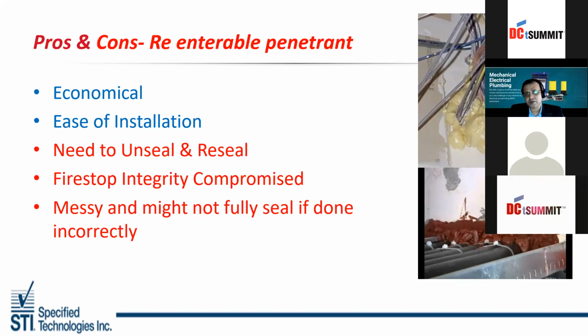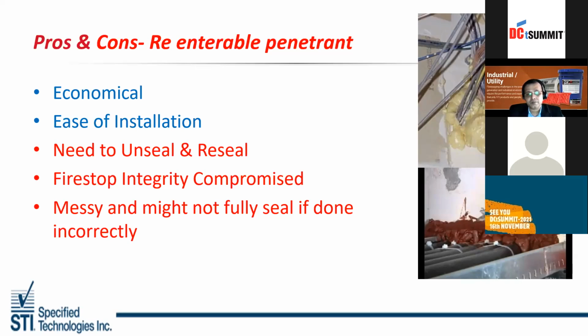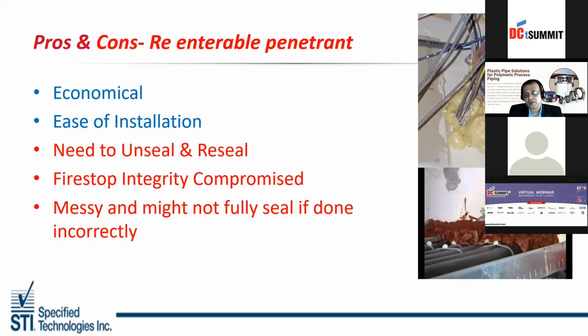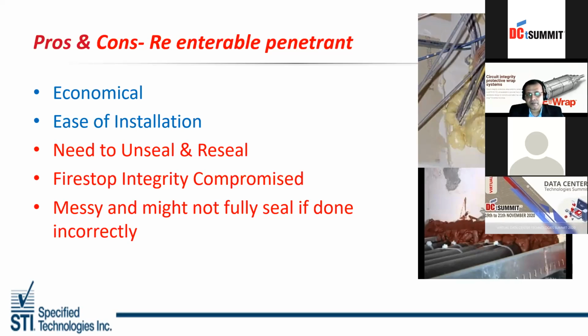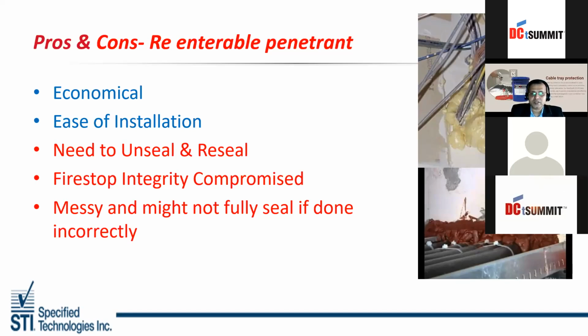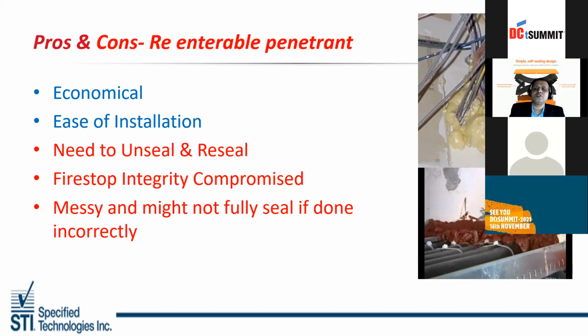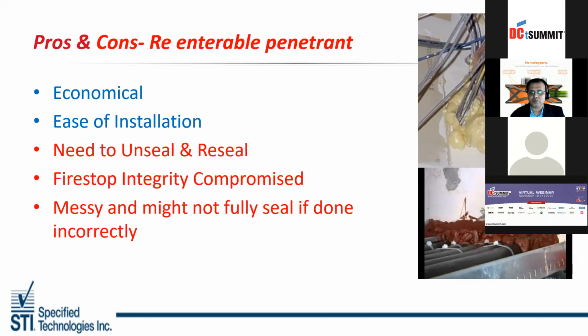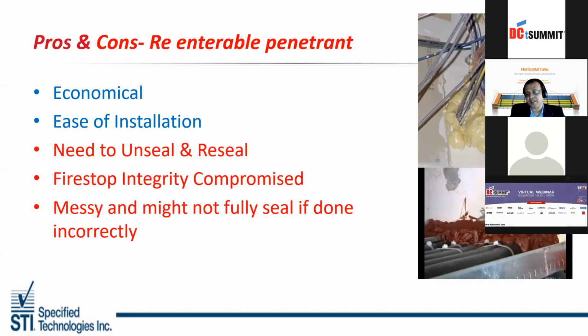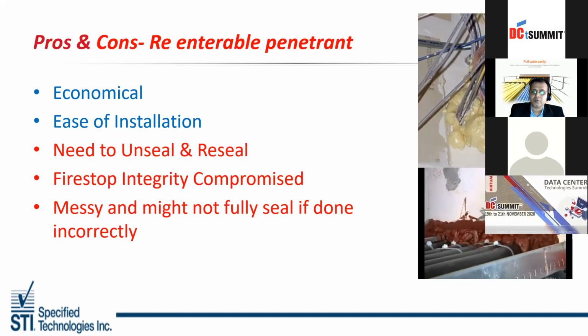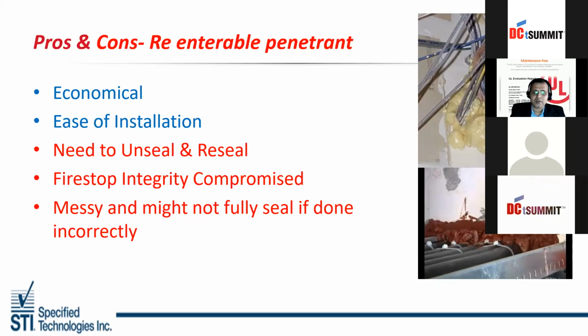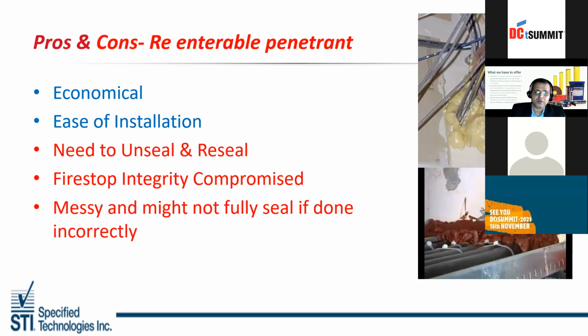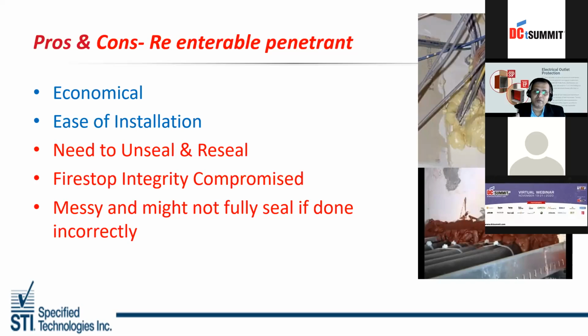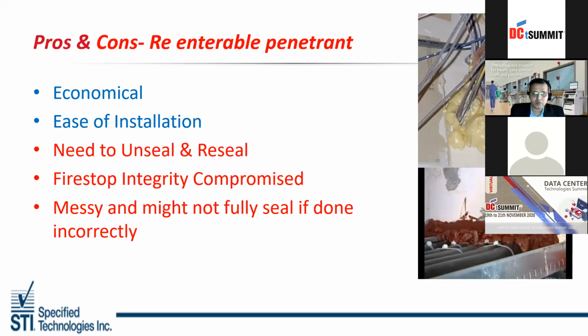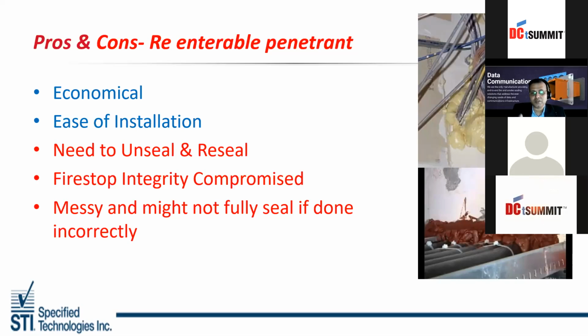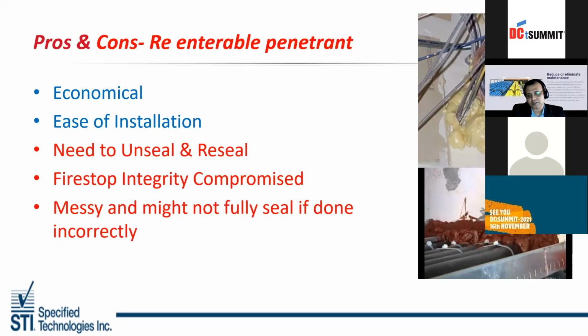So when the cable has been removed from the existing sleeve or an addition has been done, the putty has to be installed in a proper way. Otherwise, the fire stopping will fail. Here, towards your right hand side bottom, it's not installed properly because it is just kept as it is. The putty has to be installed between the concrete wall and the cables, because intumescent is like popcorn. It will expand anyway, whichever way it is. So a sealant or a putty has to be installed between the concrete wall and the cable, so that whenever the expansion happens, the concrete will obstruct the expansion going outward, and the expansion will happen inside, and it will crush the cable or the pipe which is passing through the concrete wall or a floor.